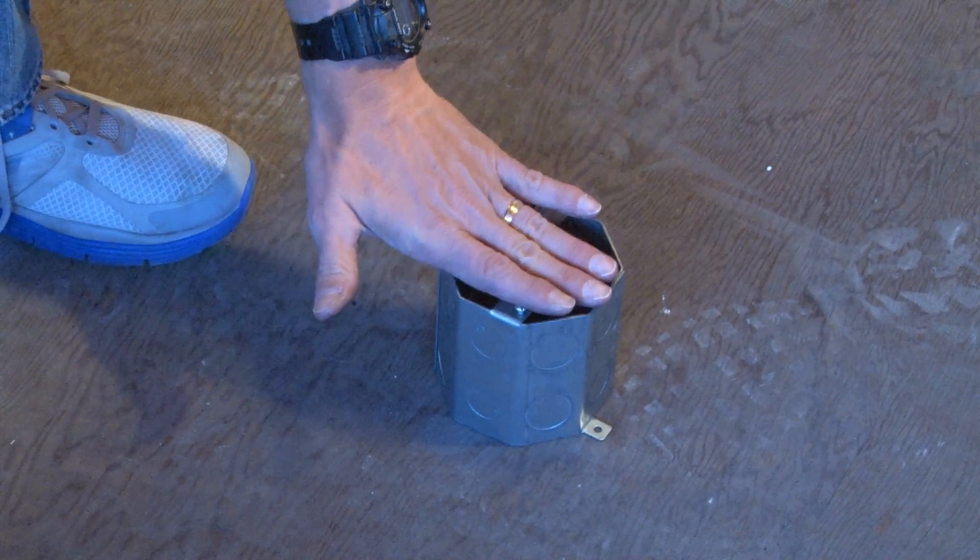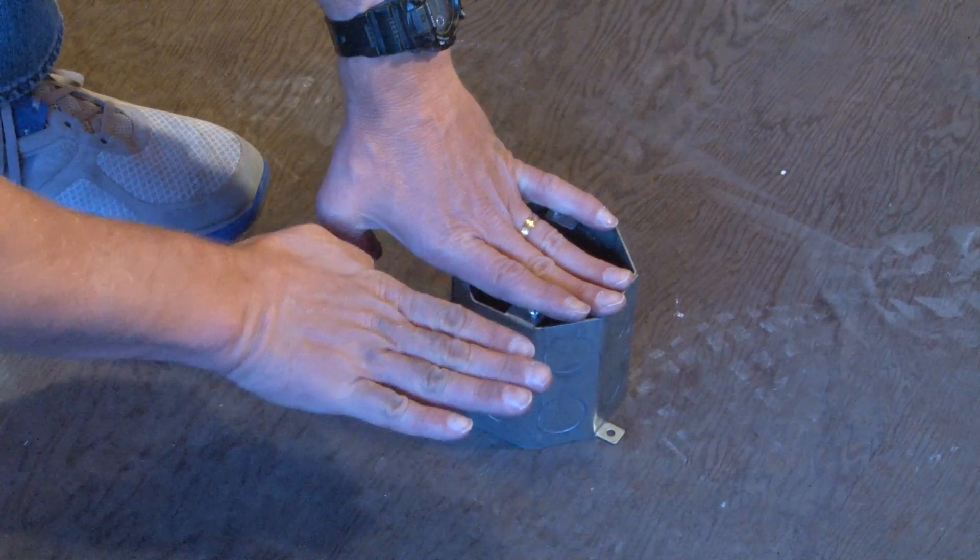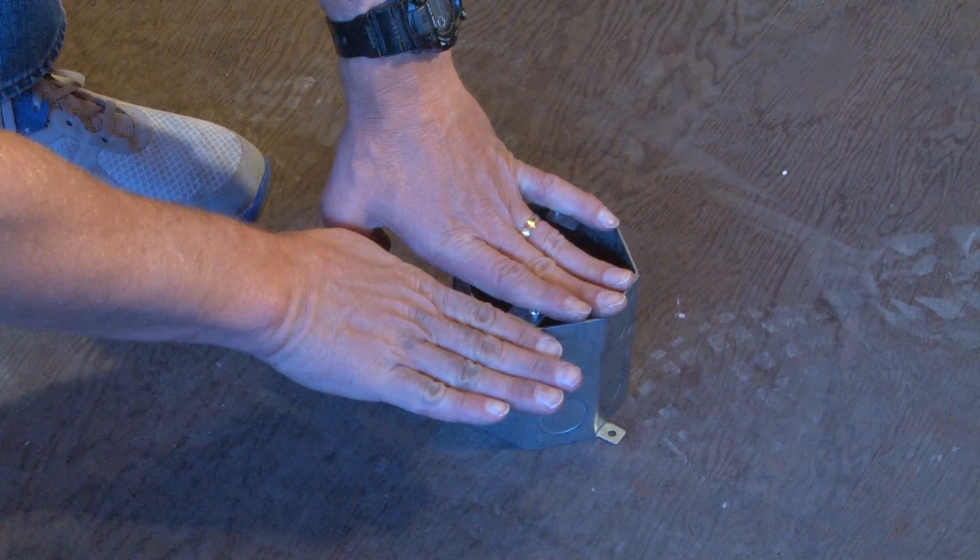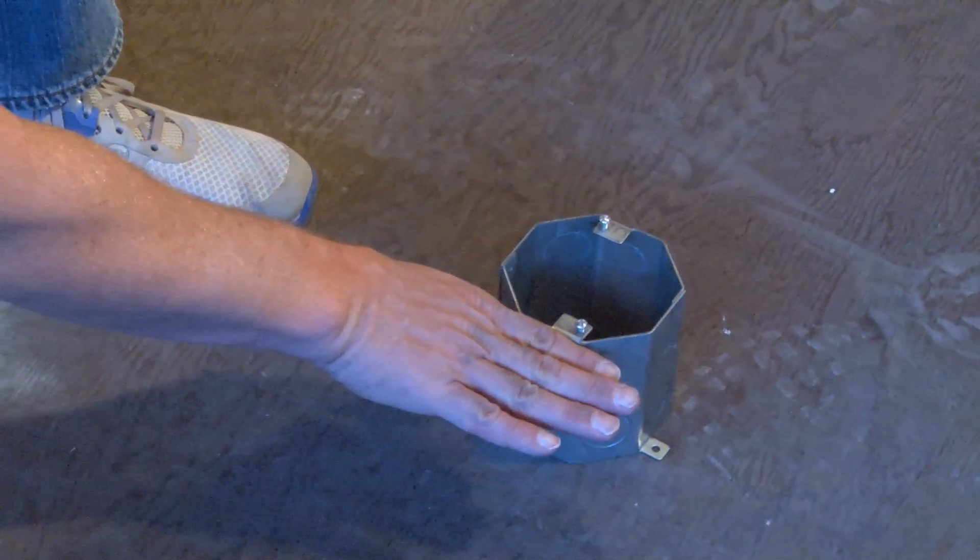Once a blank cover is put on, we're ready for the concrete pour. They pour the concrete that encases the box and the conduit, strip the form, take off the cover, and you can start wiring the box.